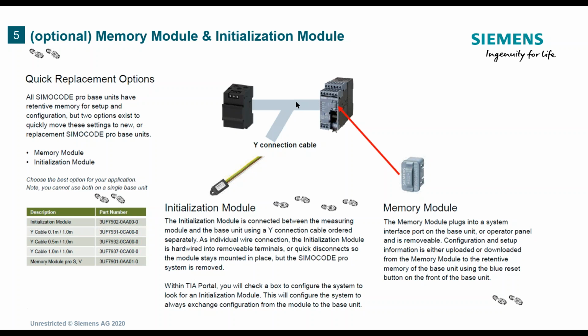What this does is it is interconnected with a new cable. The standard cable is just one point-to-point cable that goes from the basic unit to the CT or CTPT. With this one, there's a different cable that has a Y cable to it. This initialization module is mechanically drilled and attached to the motor control bucket so that nobody can pull it out of the front of the Simocode and put it in their pocket and walk away. It is mechanically tied to that motor, or if it's in an MCC bucket, it's mechanically tied to that MCC bucket space.